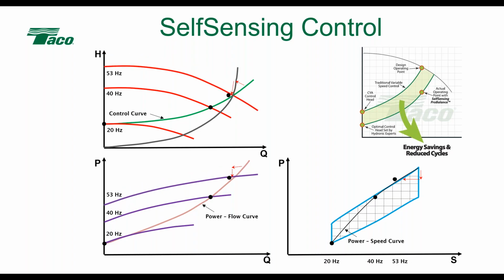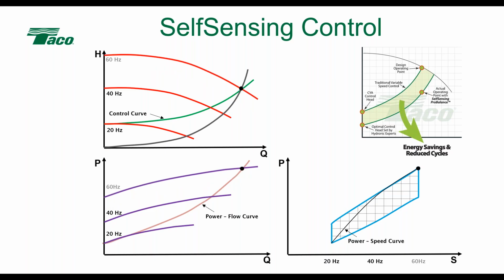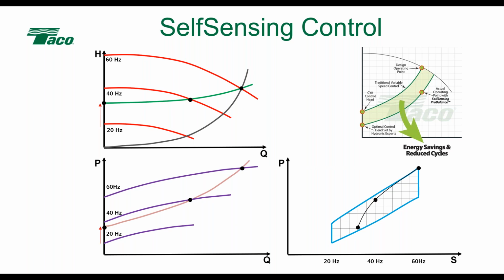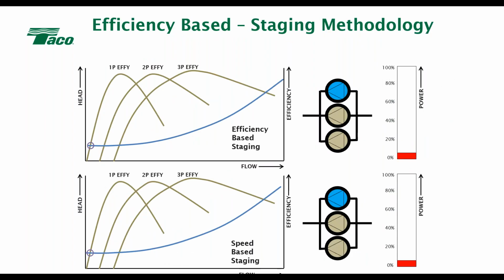Okay, and that way, as we start to slow down, now we come back onto the control curve again. And as we continue, what we'll see is that we continue to move through this as demand changes. We just move back up because the power started to change, so we increase the speed back up to stay on that control curve. And that's the real science behind self-sensing. It's not magic, I promise, it really isn't. We're using the basic affinity laws and what is happening inside that pump and motor.